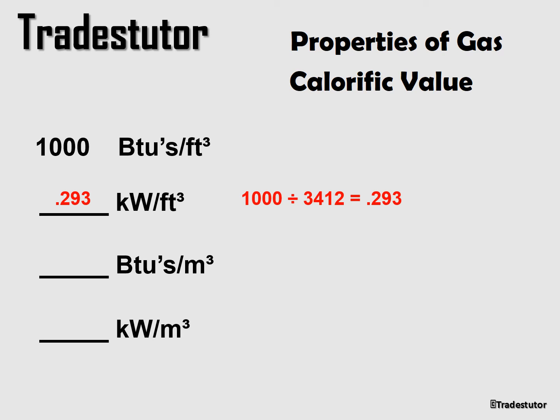The third way is BTUs per cubic meter. Starting from BTUs per cubic foot, the BTUs stay the same but the volume changes — we're increasing it. You have to think about this visually: a cubic meter is 35.31 times bigger than a cubic foot. So we take the 1000 BTUs per cubic foot and multiply by 35.31, giving us 35,310 BTUs per cubic meter.